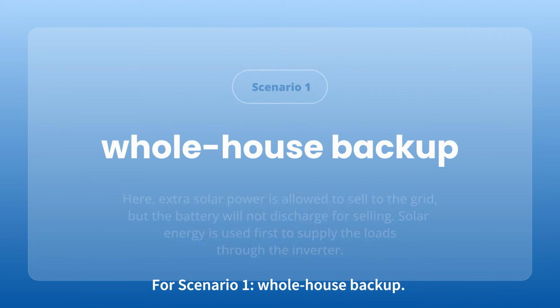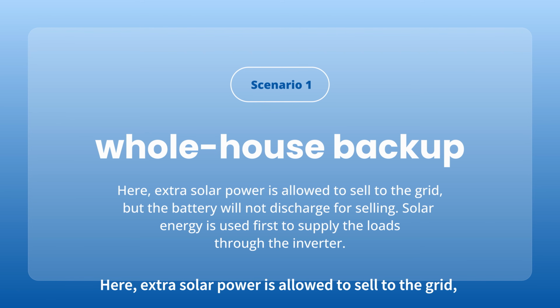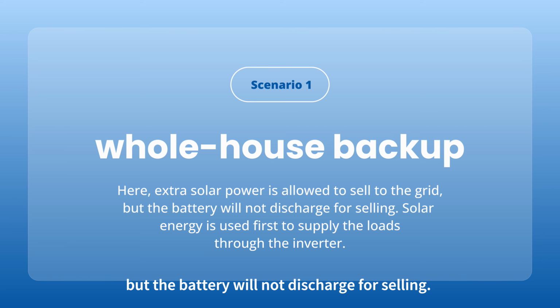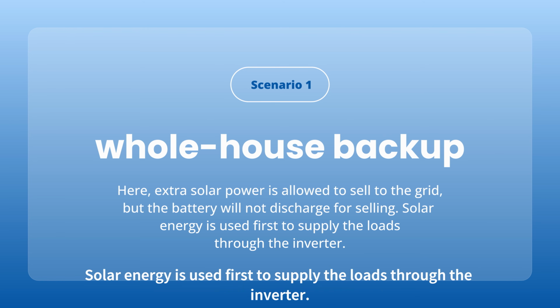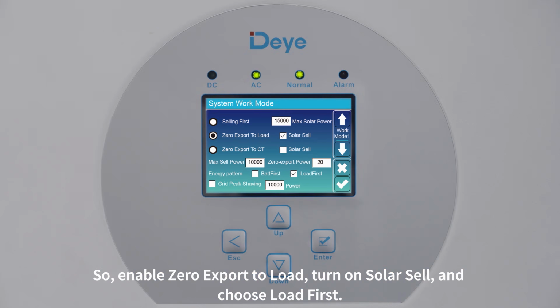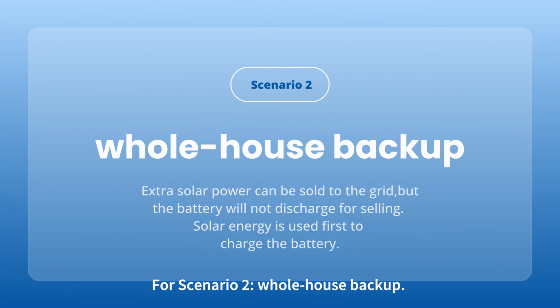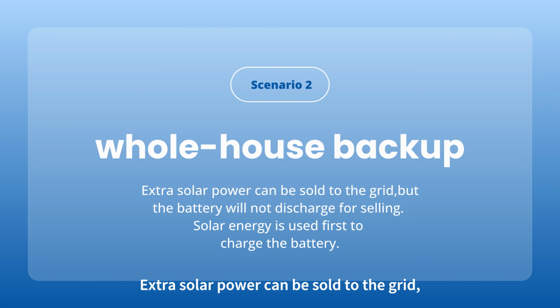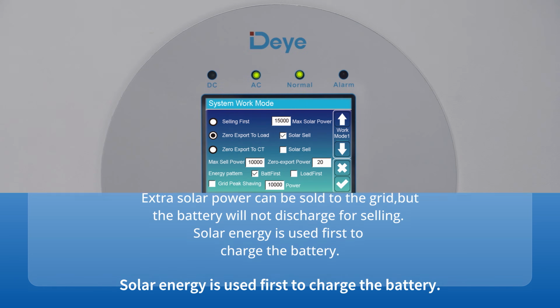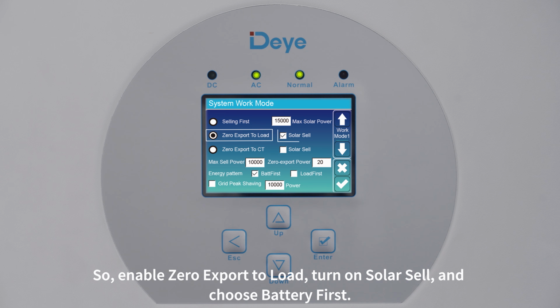For scenario 1, whole house backup. Here, extra solar power is allowed to sell to the grid, but the battery will not discharge for selling. Solar energy is used first to supply the loads through the inverter. So, enable zero export to load, turn on Solar Sell, and choose load first. For scenario 2, whole house backup. Extra solar power can be sold to the grid, but the battery will not discharge for selling. Solar energy is used first to charge the battery. So, enable zero export to load, turn on Solar Sell, and choose battery first.